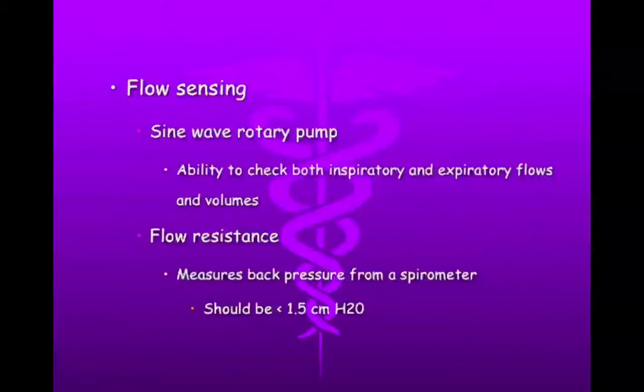Our flow sensors, there's actually a pump in a body plethysmograph, for example, that does a sine wave pumping that measures the consistency of both inspiratory and expiratory flow. So it'll push the air in and pull it out. It'll also check to see what kind of resistance there is. All machines have resistance. Anytime you put anything in front of your mouth to blow through it, you're going to have some resistance. Ideally, that resistance should not exceed 1.5 centimeters of water pressure. That's kind of the standard, so it should be less than that, so that you don't get that back pressure that can actually change your volumes or your flows that you're measuring.